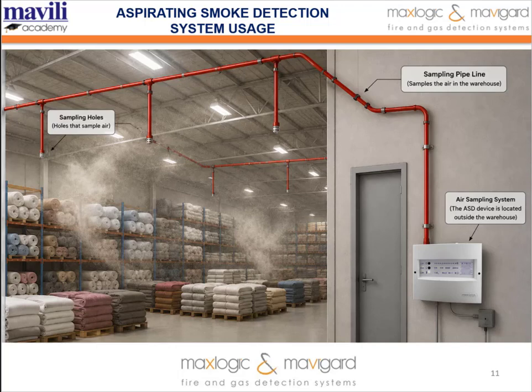Then we have maintenance process become more controlled. So system performance can be maintained by regularly checking, continuously sampling, and replacing filters when necessary. So it provides effective protection in hard-to-reach areas. Thanks to the piping system, air samples can be taken from areas with high ceilings or shelves, or where equipment placement is difficult.